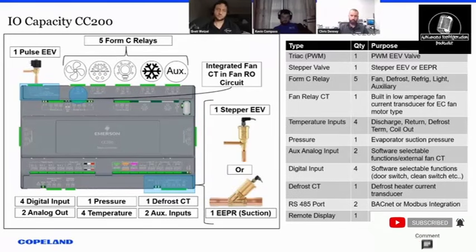As soon as we get that communication, we make the shift, and the case controller just goes right into ultra low superheat mode. And then we have some safeties built in there. If it were to drop offline, or if it were to sense that E2 or E3 isn't there for a specified amount of time, then it'll go ahead and exit out of that mode and go back to regular superheat.